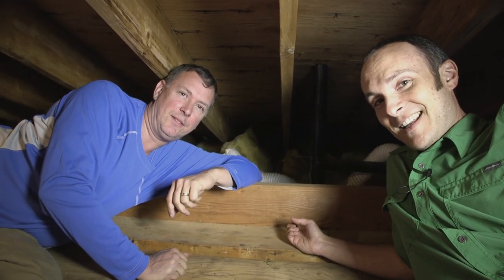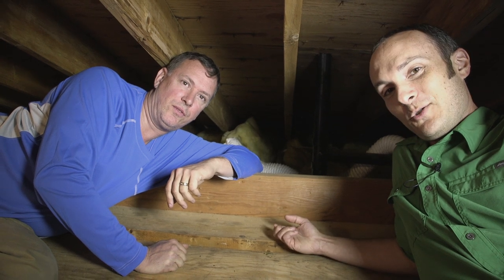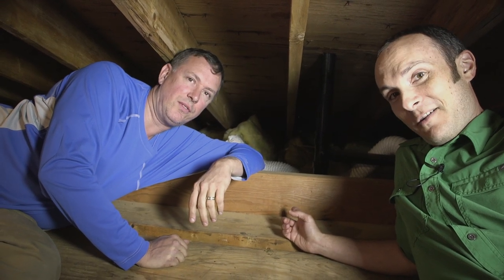Incidentally, if you were to add more insulation to your attic, but not air seal it first, you could create this moisture problem that we're talking about, which is that you cool down the surfaces in the attic, and now it would be colder and would condense the water that's coming up there in the air that's inside your house. So this is why we really want to be careful about doing good things to a home's performance without testing. Right behind this dam, that's the end of our floor, are a couple of things that are magic.